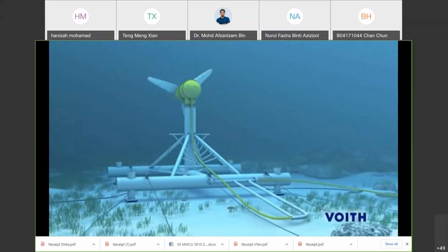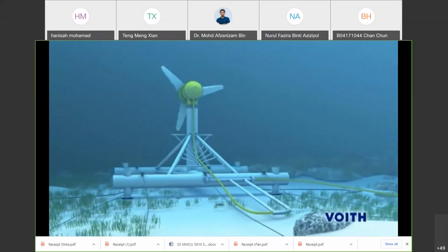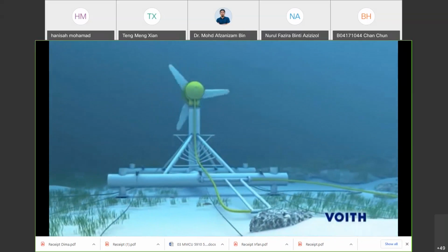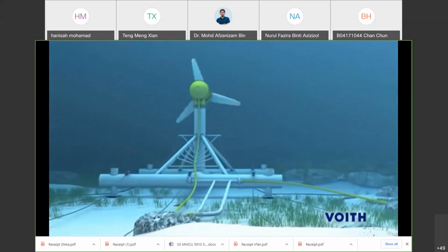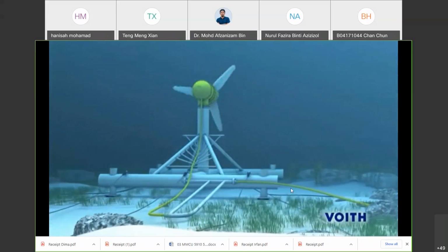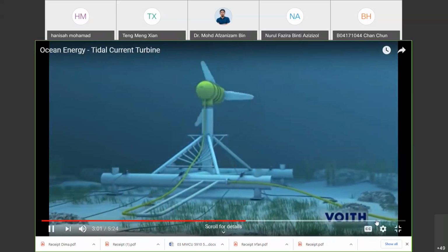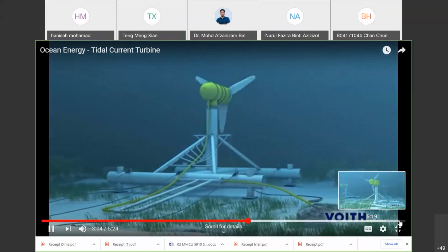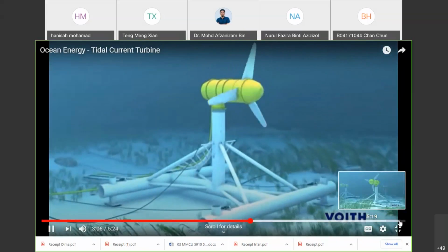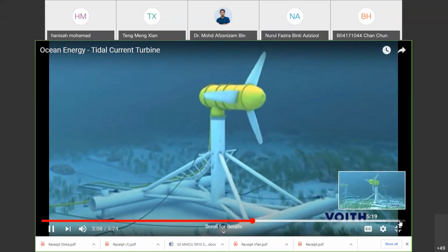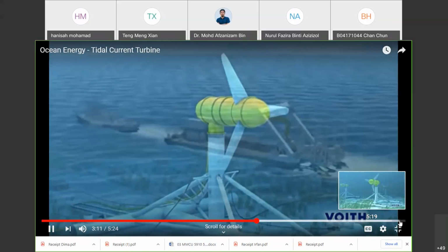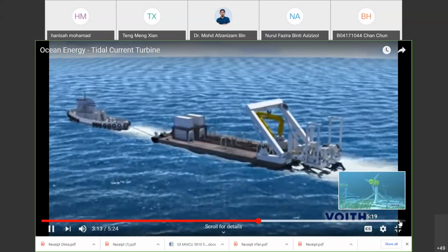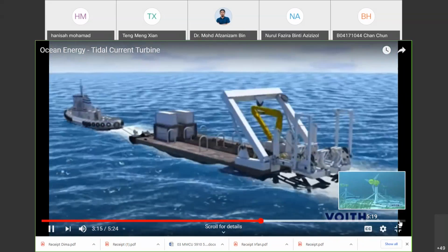Via the sea cable, the generated electricity is directly transmitted to an onshore inverter station, then fed to the grid via a transformer. This robust and simple subsea technology gives long intervals between maintenance and hence minimizes the utilization of extremely expensive marine equipment. When the tidal current turbine is due for maintenance, the facility is shut down and disconnected from the grid on shore.